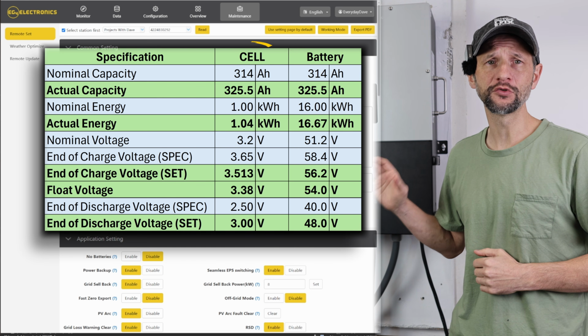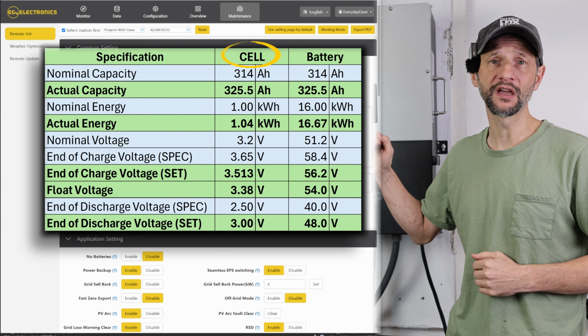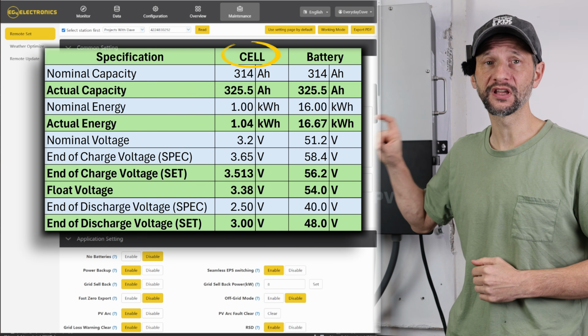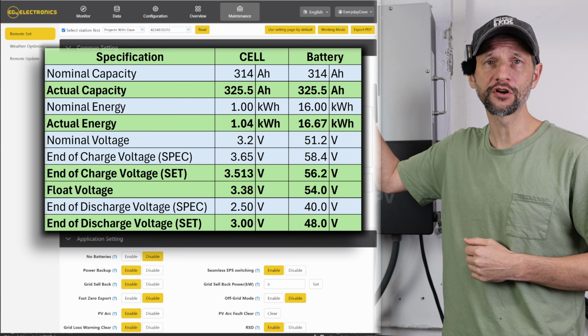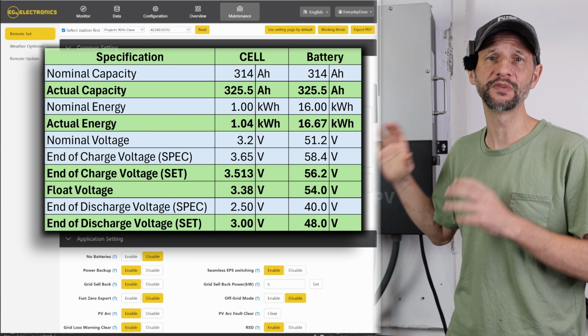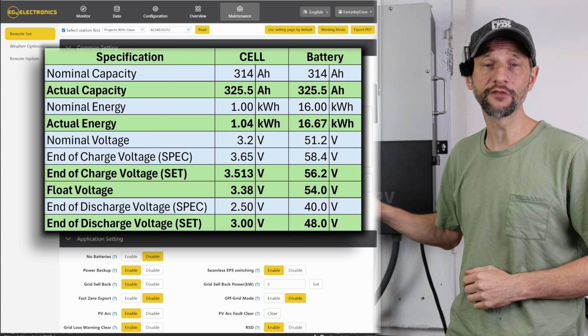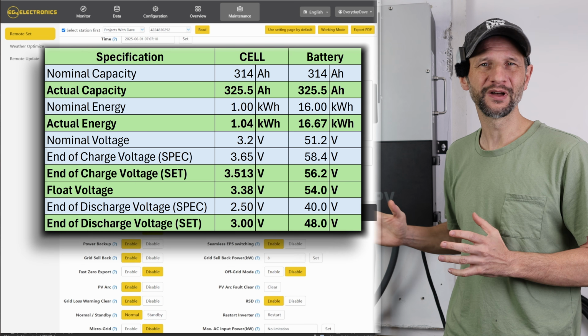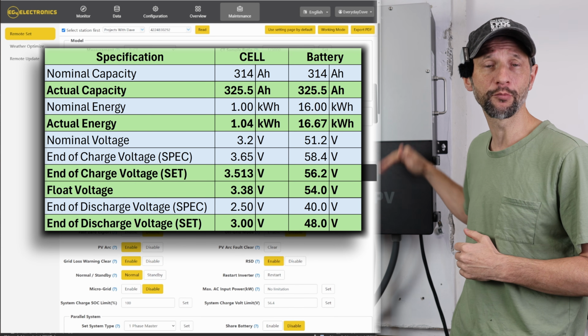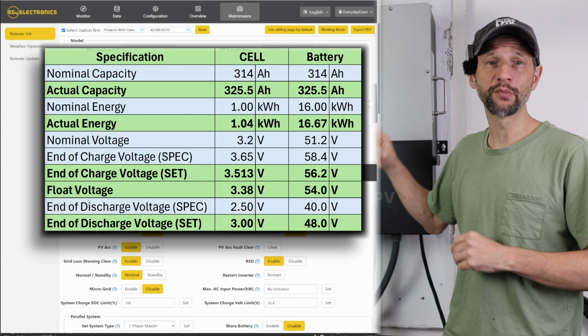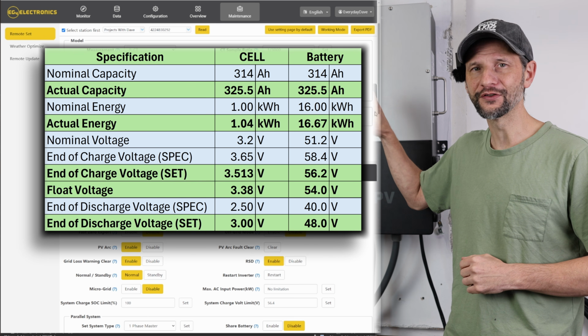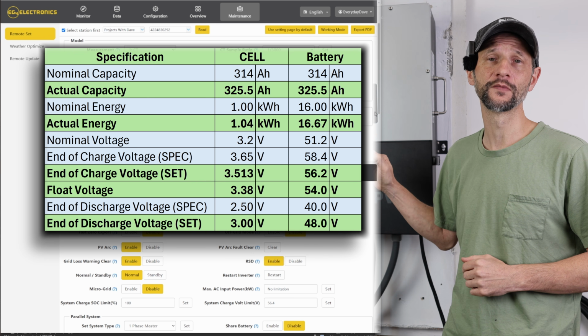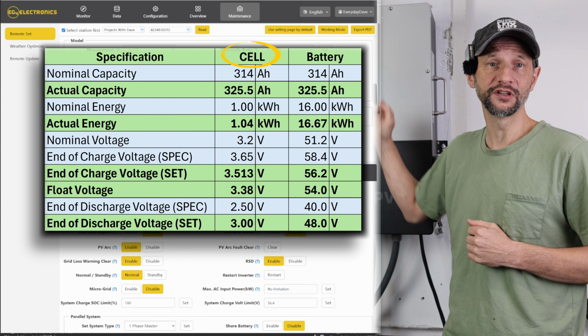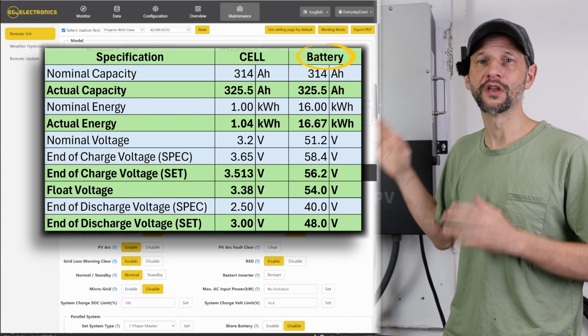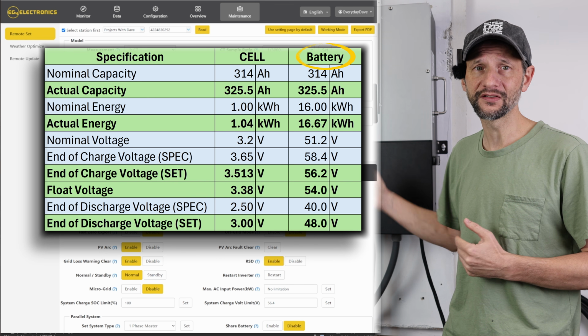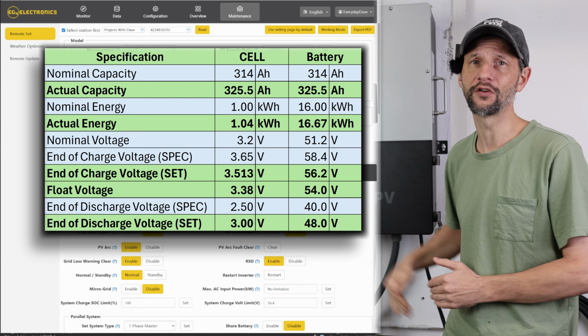At the battery module level, we want to set the JK-BMS to the specified setting for your particular cell. I want to use the maximum charge and the minimum discharge voltage because the BMS is there to protect the battery from overcharge or over discharge, but I don't want it to interfere with my day-to-day operation at the inverter level. This chart combines the battery specs for reference with my actual settings in the inverter. The cell column is the value for an individual cell, and the battery column is just the cell column times 16, since our entire battery assembly is all the batteries in series.